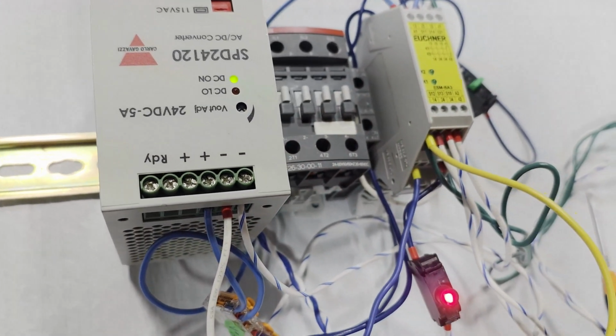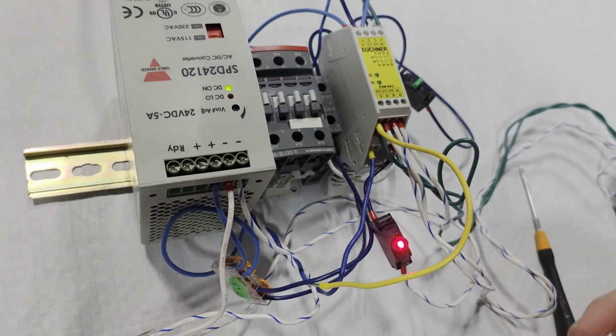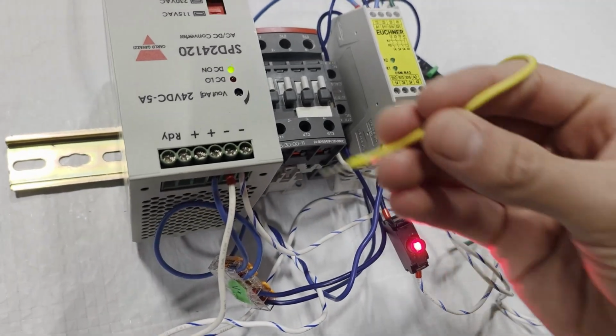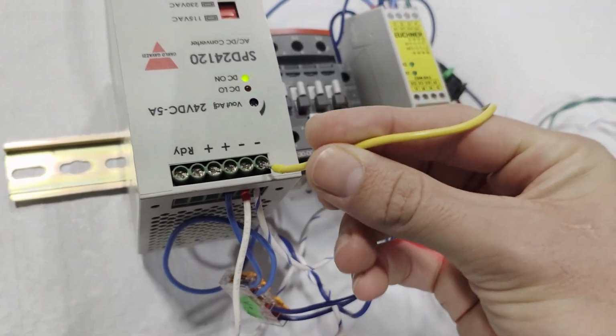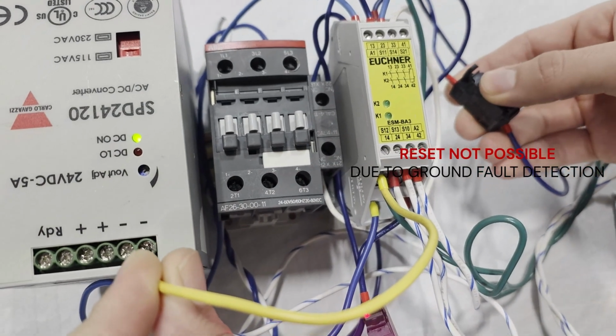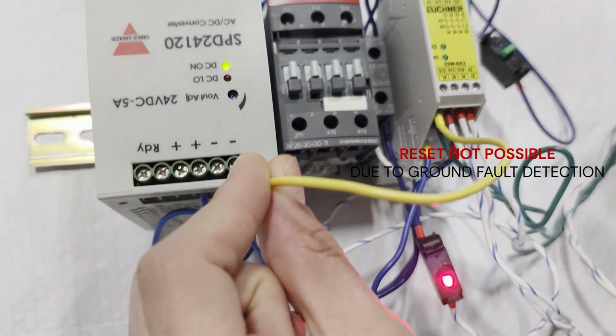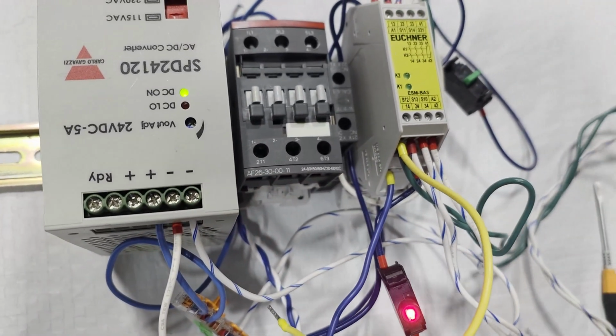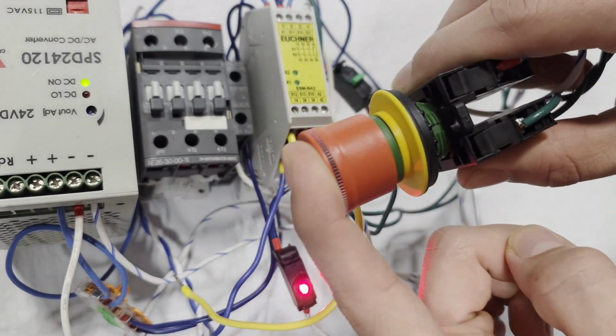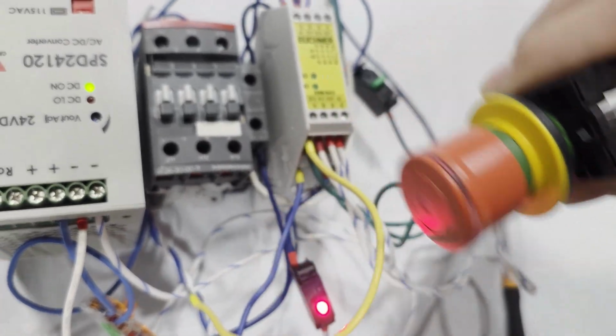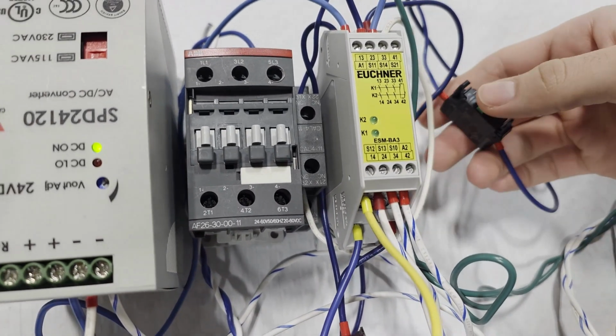Okay, that E-stops it. Now if you keep holding it to ground and try to reset with the other hand. Yeah, it should not reset. So we have to clear the fault. Yeah, now it should reset.